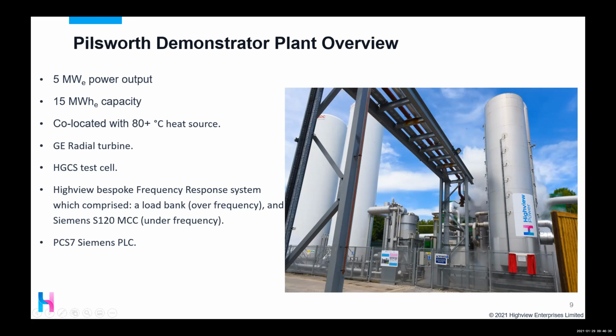So we got another grant subsequent to that, and we built a frequency response system which comprised a load bank for overfrequency and a Siemens MCC which worked with ultracapacitors and flywheels to provide under-frequency response. And the brains of the operation is a Siemens PLC, PCS7.